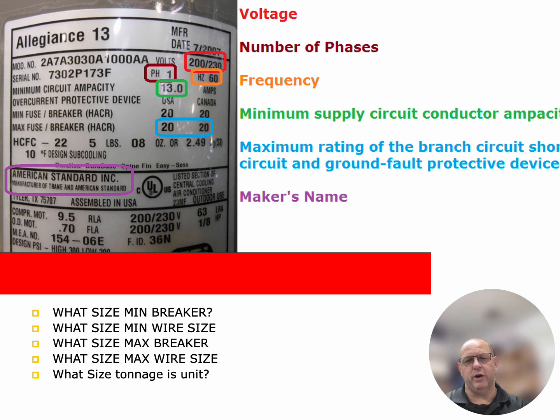So, couple of questions for you. What size minimum breaker can I put on this unit? I'll give you a couple of seconds to think about it. We're looking at the nameplate. We come up here to the minimum fuse, minimum breaker, and we find out that this particular system, the minimum breaker that we can put on it is a 20 amp breaker. Now, taking your knowledge back to electrical, 14 gauge wire. Okay, 14 gauge wire can hold up to 15 amps.